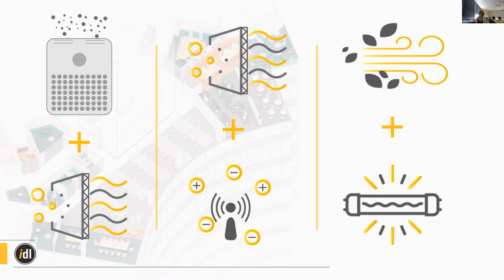Another great pairing of technologies would be upgrading your MERV filter and implementing needlepoint bipolar ionization. Because we don't know about the efficacy of needlepoint bipolar ionization, or there's not as much research, it's going to be harder to install that right. So upgrade your MERV and then hope that the needlepoint also does its job. Another great pairing, increasing the outdoor air intake, short term obviously, and also putting a UV light on your cooling coil so that cooling coil stays clean and you can increase the capability of heat transfer on the cooling coil.